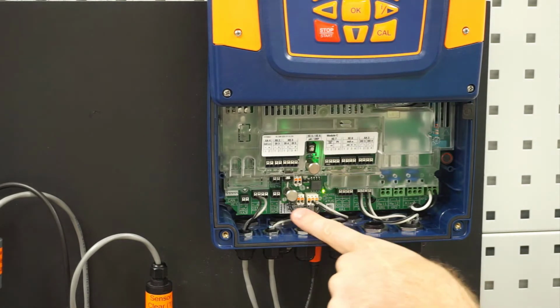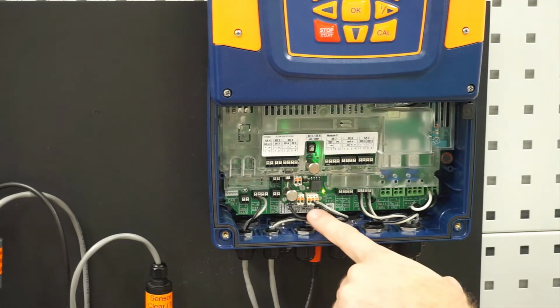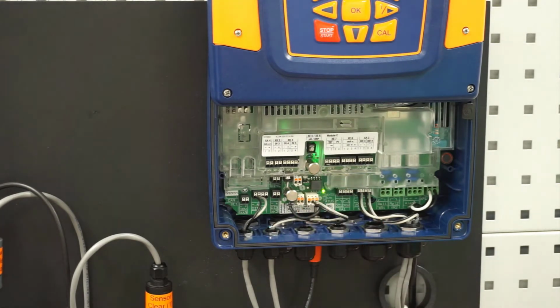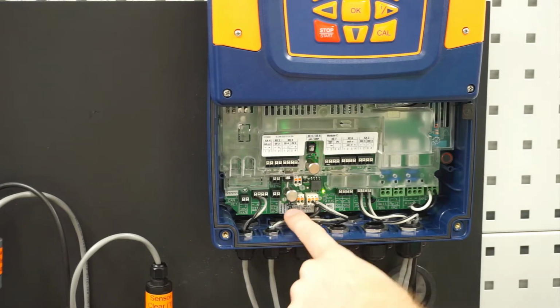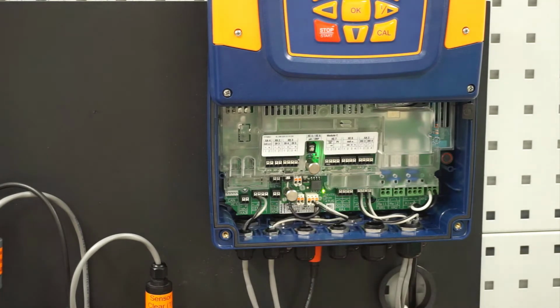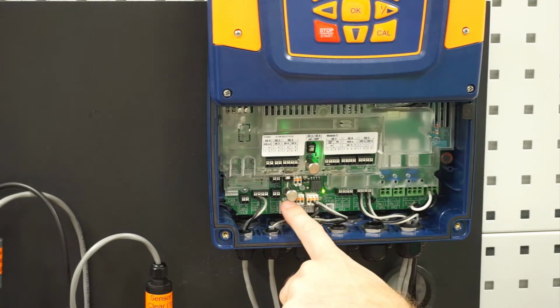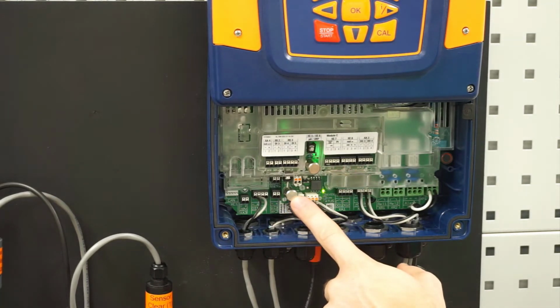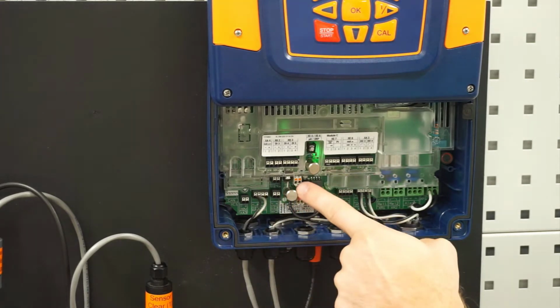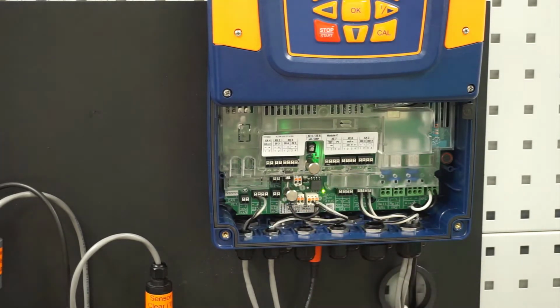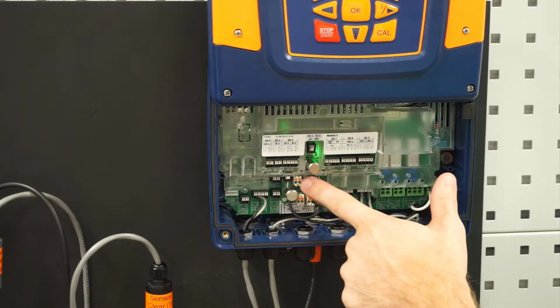Next thing we see wired up here is on this card that's raised out a little bit. We do have different options for cards. In this particular case, we have a millivolt, milliamp card. So on the left side of that card is where we bring our pH sensor, and that pH sensor is sending the controller a millivolt signal. So we land the shield underneath this clamp here, and then the actual wire to the controller goes up into the terminal above it. Also on here, we're not using, you can see there's a jumper here.